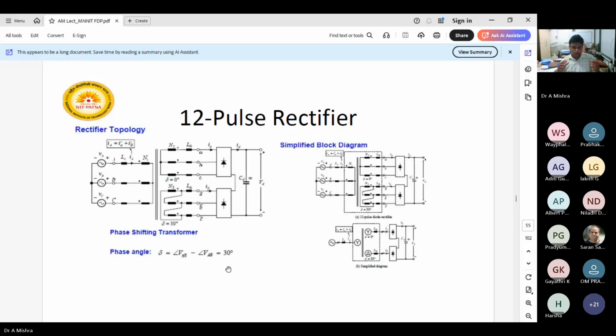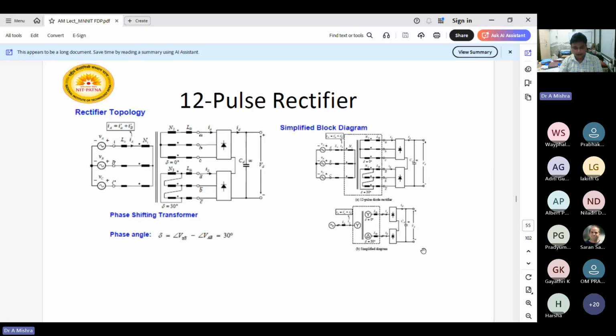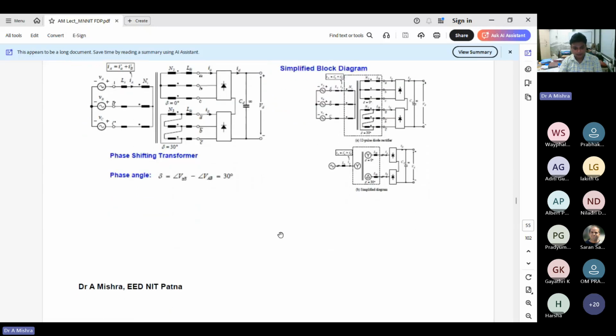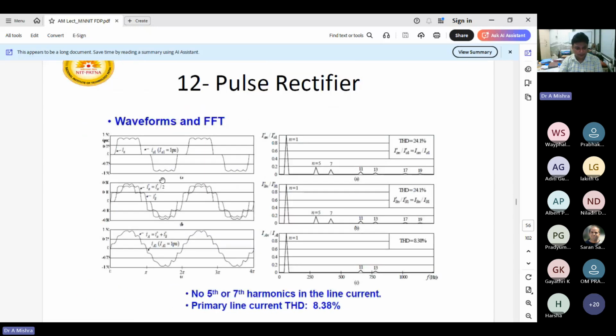That's all. So these are the two. This is one 6 pulse converter. This is another 6 pulse converter connected together by the phase shifting transformer. These two are getting the input voltage with the 30 degree phase difference and the output will be combined together. One will be connected in star, another one is connected in delta, and the output is combined and you will get the output. This is the output of a 12 pulse rectifier.